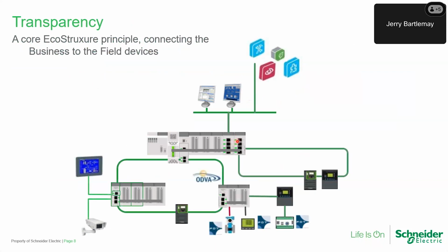A request for data would come down into an Ethernet module, and the CPU would typically act as a data concentrator. So it would have to request data from the field devices and hold it for that asset management system, for SCADA system, for historian, for process optimization software, what have you. Meaning there's additional work and additional loading on that CPU over and above the control task that it's doing.